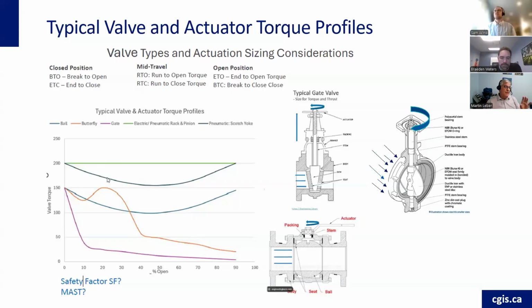But when you think of it, a big ball valve that is always interfacing with the seats of the valve requires a higher torque than any of the other valves to get it to stroke through those seats for the whole stroke of the valve. So the sizing on this, you have to think about a little differently, depending on how long it takes for it to go from open to close. In that case, you'll be sizing on the torque required in mid travel. So this is just a brief overview again of the torque profiles of the different types of valves.